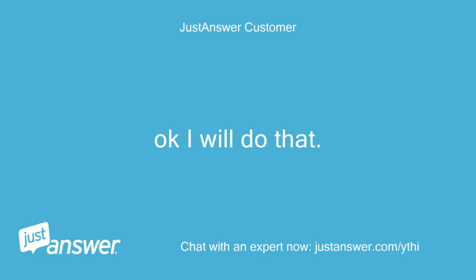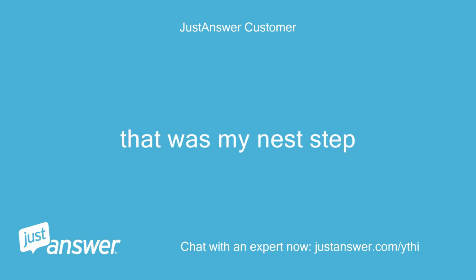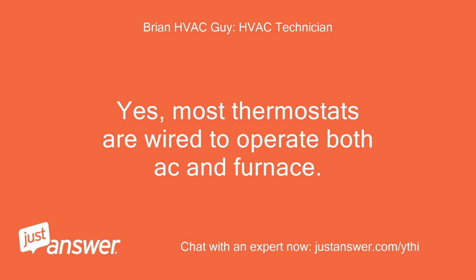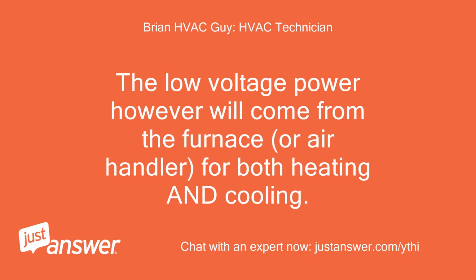Okay, I will do that. That was my next step. Yes, most thermostats are wired to operate both AC and furnace. The low voltage power, however, will come from the furnace, or air handler, for both heating and cooling.